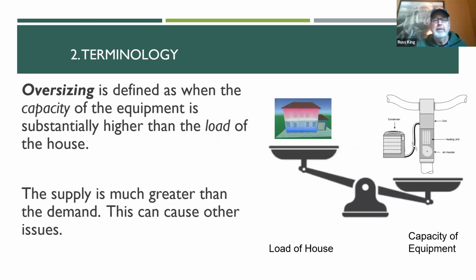Oversizing is defined as when the capacity of the equipment is much too big for the demand of the house. So your supply is much greater than the demand. This can actually cause comfort issues as well, and it's less energy efficient. So like I said, there's a fine line. You don't want to be too big and you don't want to be too small. You don't want to be oversized and you don't want to be undersized.